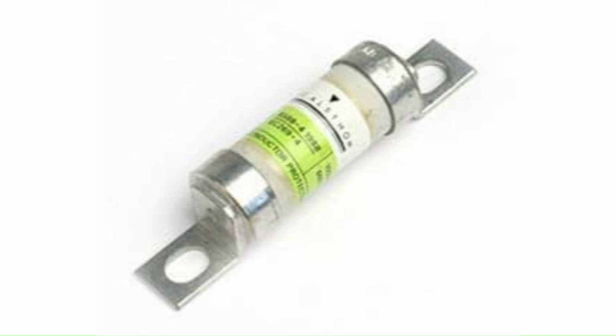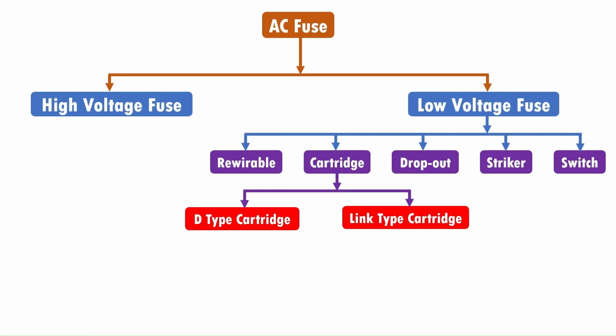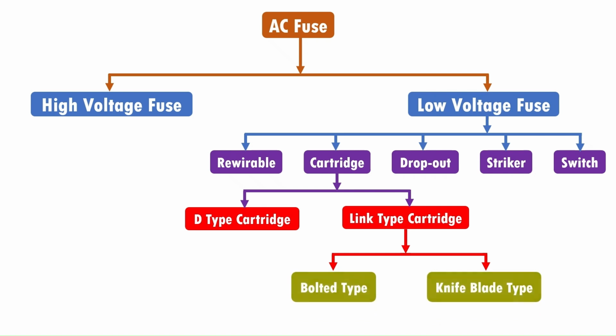Silver and copper wire is used for making the fuse wire. For increasing the breaking capacity of the fuse, two or more silver wires are joined in parallel with each other. These wires are adjusted in such a way that only one wire will melt at a time. The HRC fuse is of two types: knife blade HRC link fuse and bolted type HRC link fuse.